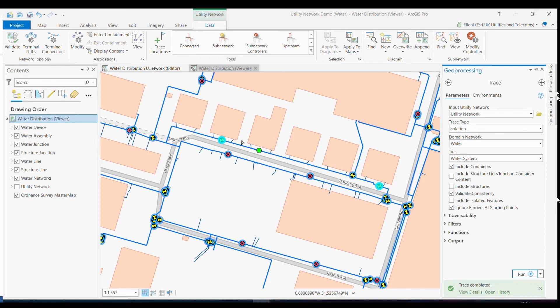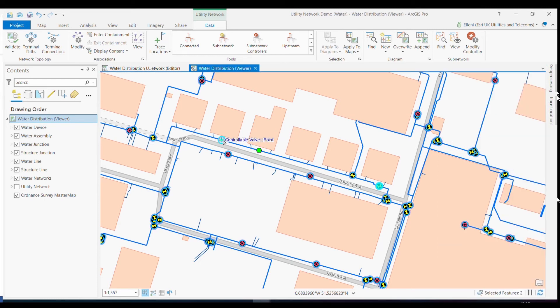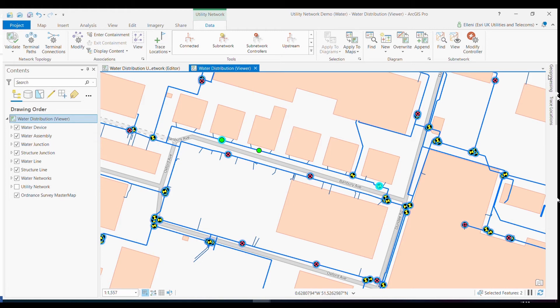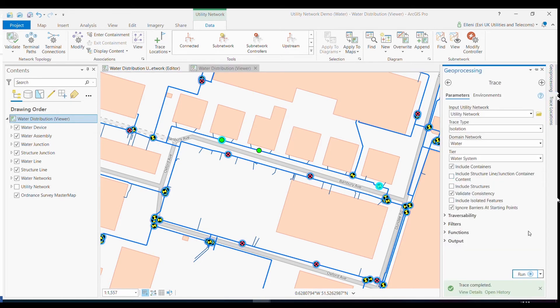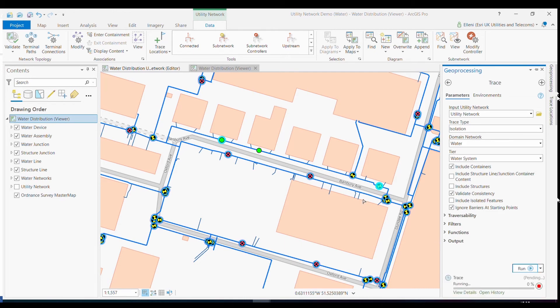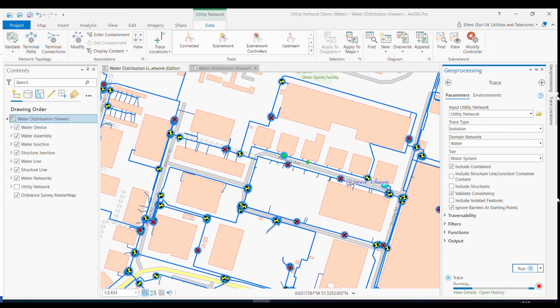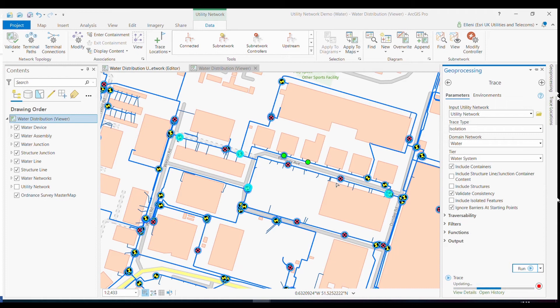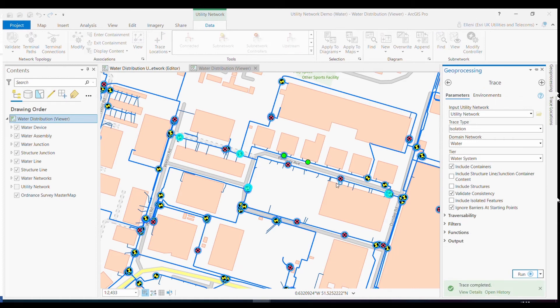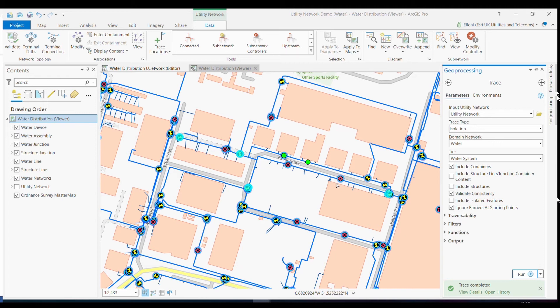And in this case, I know that this particular valve has in fact been paved over. So we need to rerun that trace and find the next operable valves that the engineer needs to attend to. By simply selecting that valve as another trace location, the tool recognizes that as a skippable location. And once the tool has finished running, you'll see that actually now we have a completely different set of results, where the impact of that inoperable valve has meant I need my engineer to switch four valve locations off in order to successfully isolate the incident.